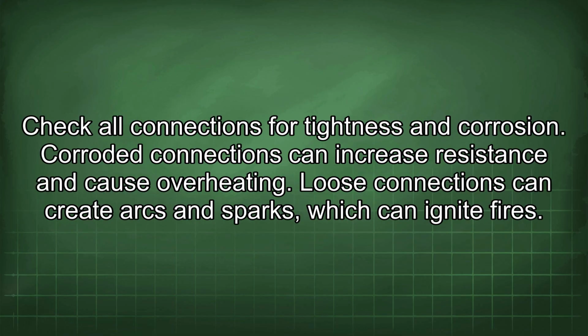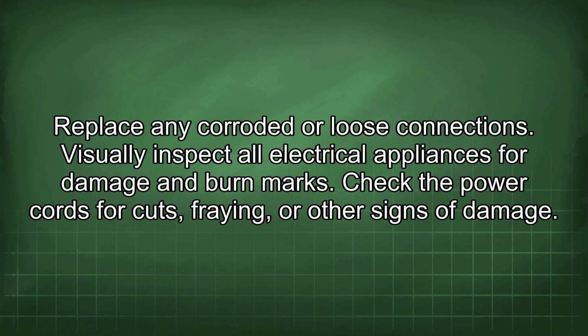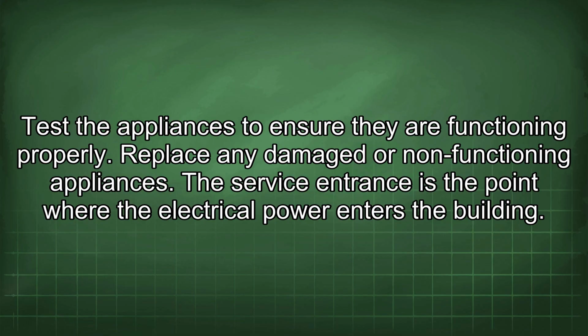Check all connections for tightness and corrosion. Corroded connections can increase resistance and cause overheating. Loose connections can create arcs and sparks, which can ignite fires. Replace any corroded or loose connections. Visually inspect all electrical appliances for damage and burn marks. Check the power cords for cuts, fraying, or other signs of damage. Test the appliances to ensure they are functioning properly. Replace any damaged or non-functioning appliances.